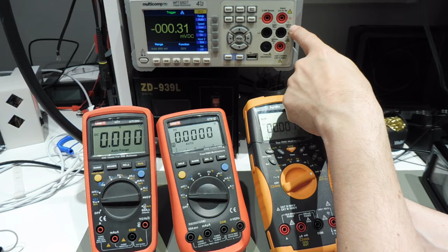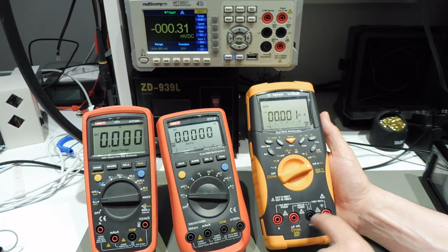That's the difference to these ones here. They still reach a specification of 1000 volt even in AC mode, so you can measure 1000 volt AC, which in reality has a much higher peak voltage. This meter here cannot do that. So that's important to look at. Also to notice here, this one is also fused only with 250 volt AC, so the current ranges are also only for 250 volts. So that's also important to know. This one here, as far as I remember, has a fuse really rated for 1000 volt inside for these ranges.